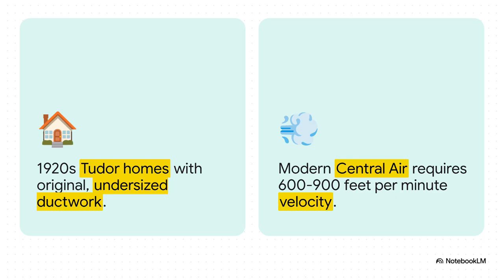Here is the core architectural conflict. Picture vintage 1920s Tudor homes equipped with tiny original ducts, going head-to-head with modern air conditioners that desperately need to push air at 600 to 900 feet per minute. It's like trying to breathe through a straw while running a marathon. That's exactly what happens when you force modern, high-capacity central air through ductwork designed decades ago, maybe just for gravity heating. The system chokes, the air handlers struggle, and rooms far from the furnace stay completely uncomfortable.